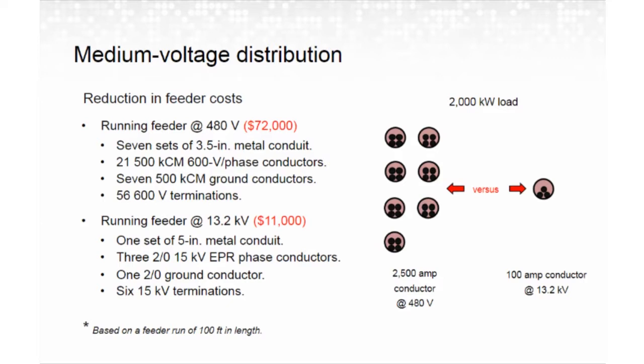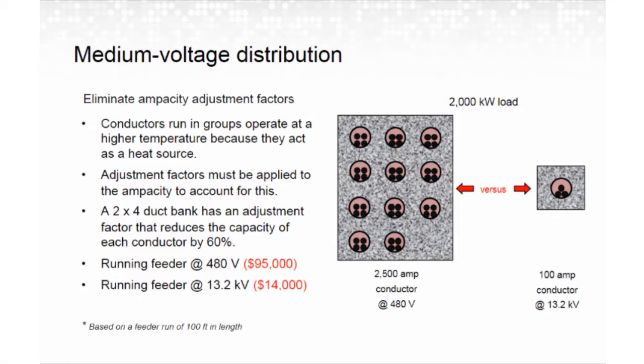Let's take a look and see what happens when we put this underground. When the same feeders are placed underground, temperature derating needs to be considered. Because the conductors heat the duct bank and thus mutually heat each other, NEC requires that ampacity adjustment factors be applied. Now, these adjustment factors reduce current handling of the installed wire. So while in air, in conduit, a conductor will have a rated ampacity of X, when you put it in ground and encapsulate it in insulation and then heat it from other conductors, that ampacity is going to reduce. And heat loss is simply another way to look at lost energy.